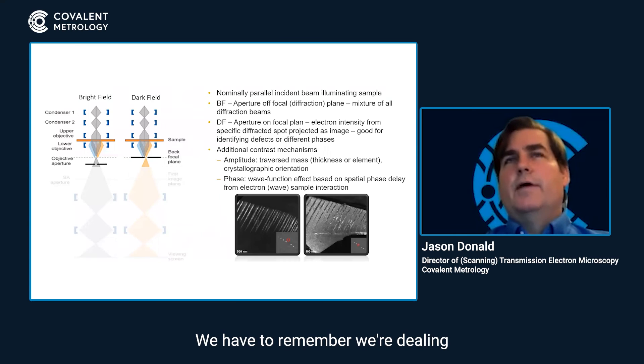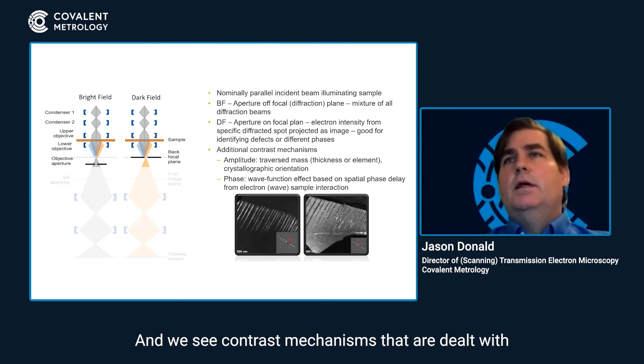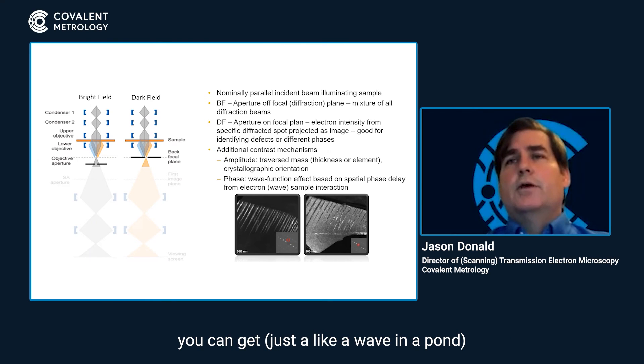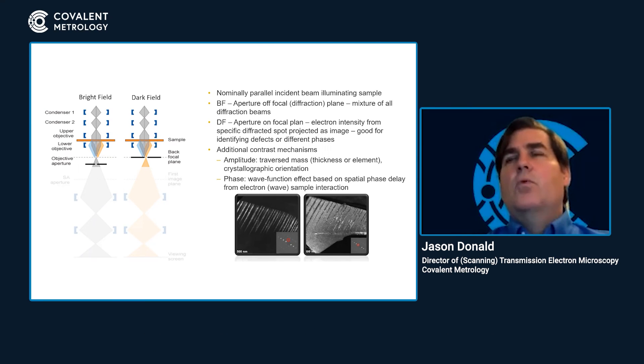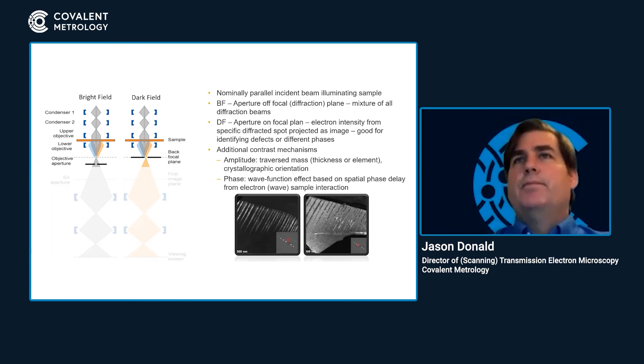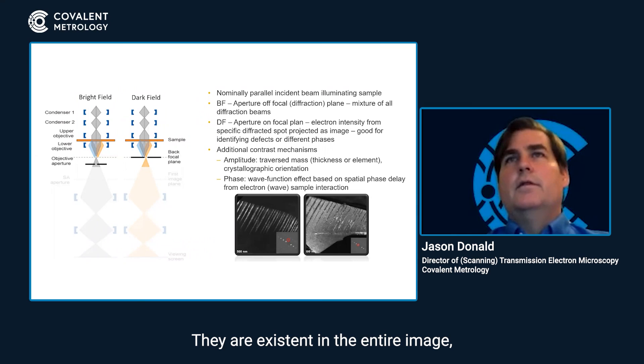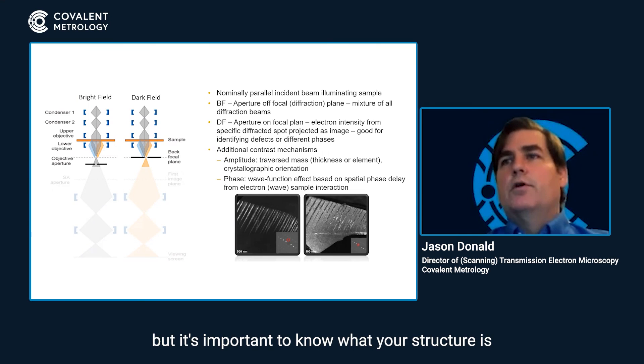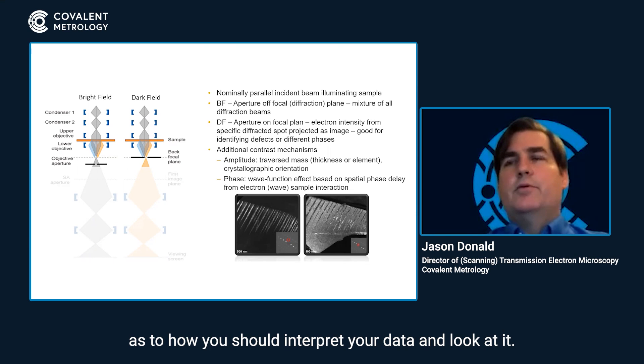The second contrast mechanism is phase. We're dealing in the quantum mechanic world where electrons can be treated as either a particle or a wave, and we see contrast mechanisms that arise from the sample interaction with the crystalline structure. Just like a wave in a pond, you can get constructive or destructive interference, which can impact the nature of what you see and the contrast. All TEM images have a combination of amplitude and phase contrast — it's important to know your structure, as that will help you interpret your data.